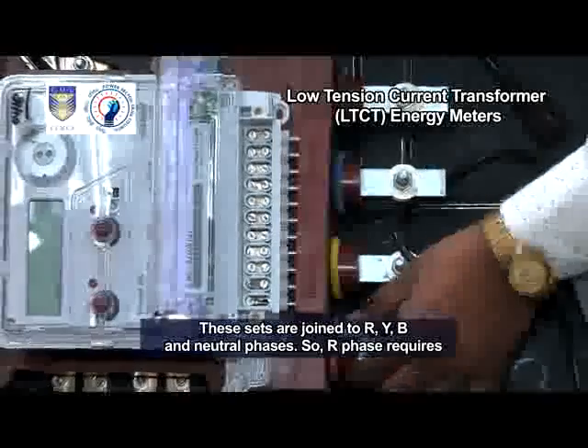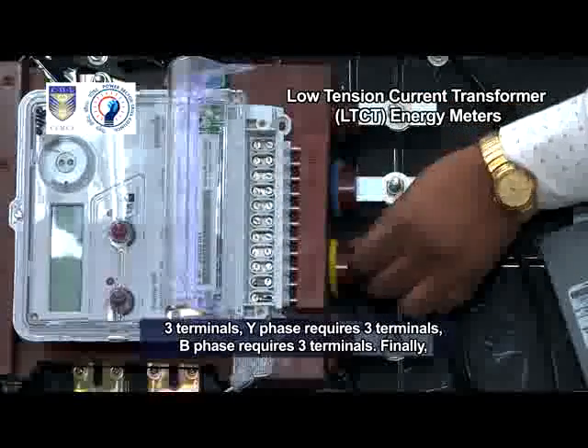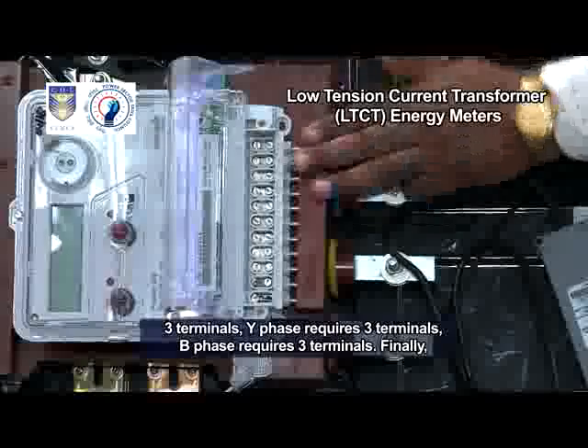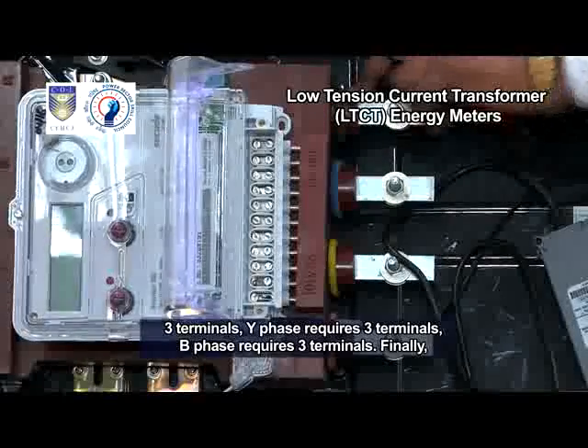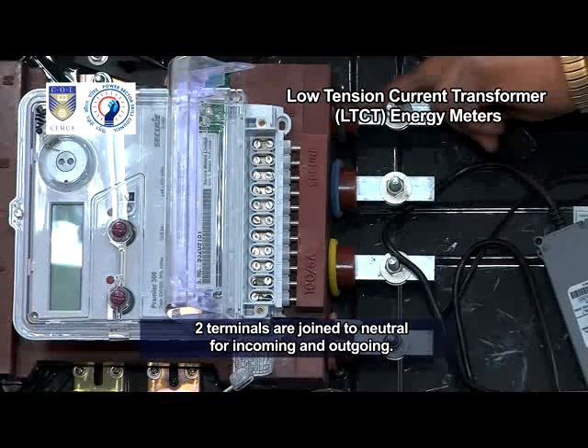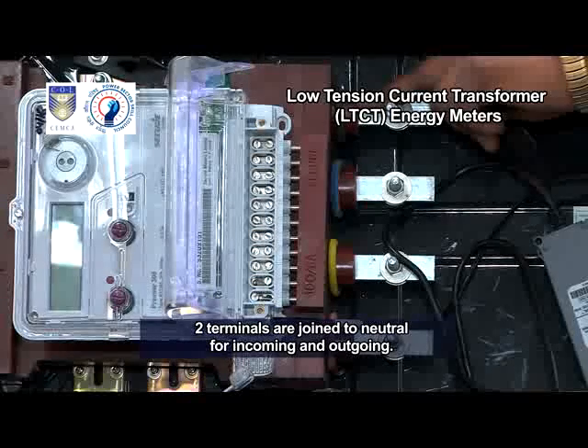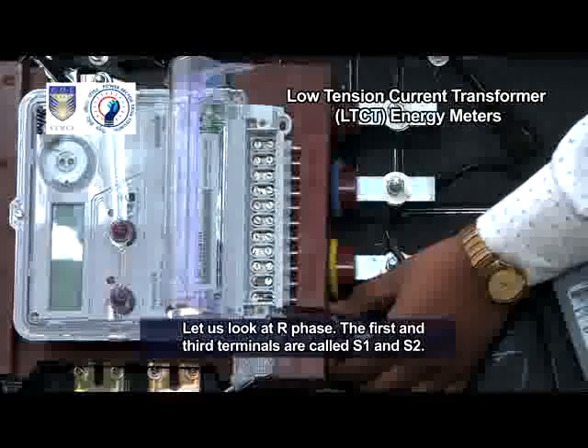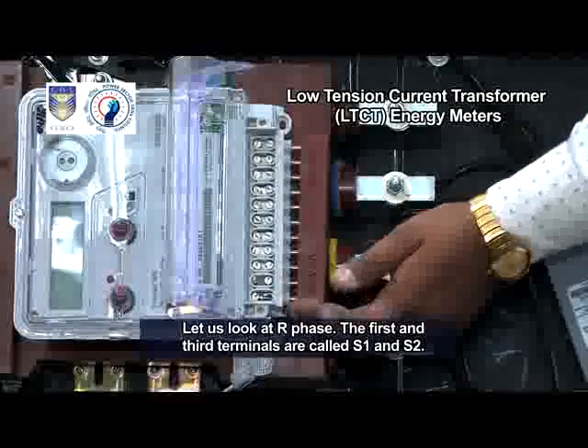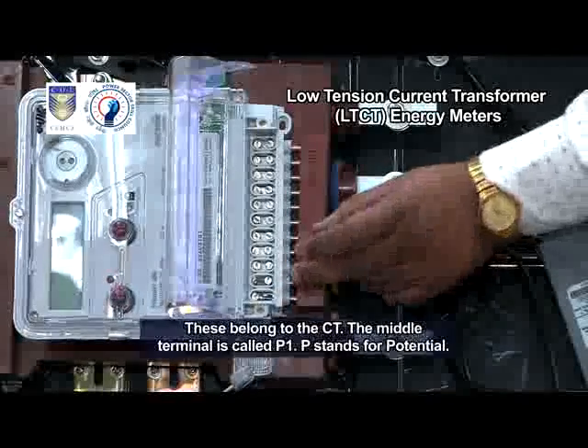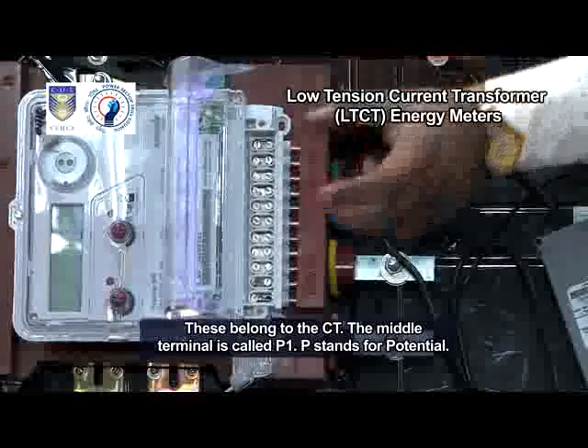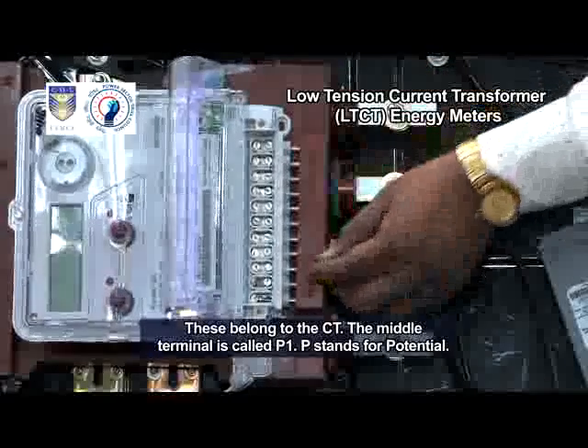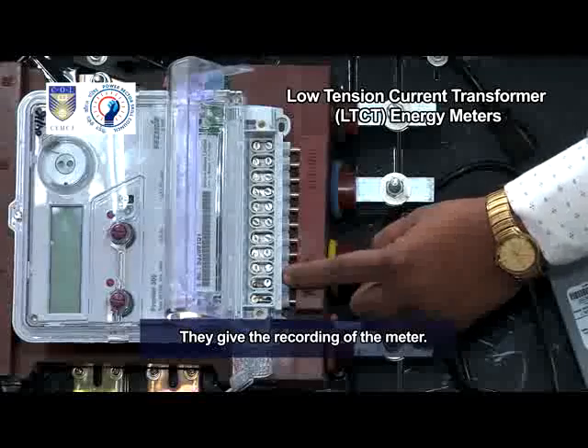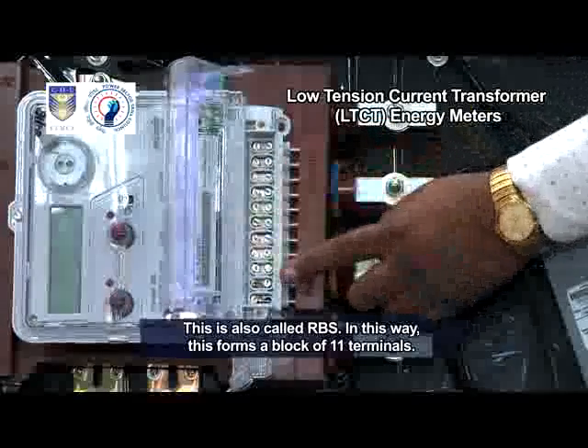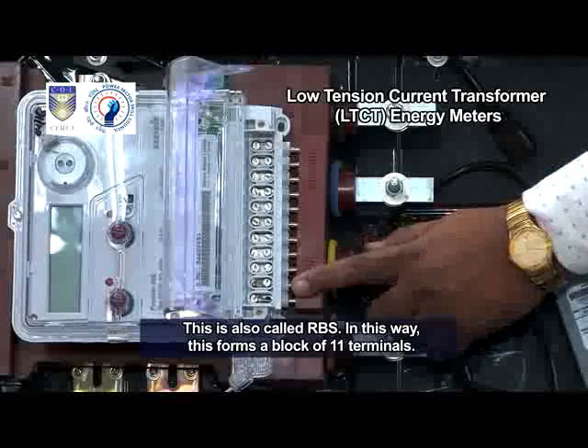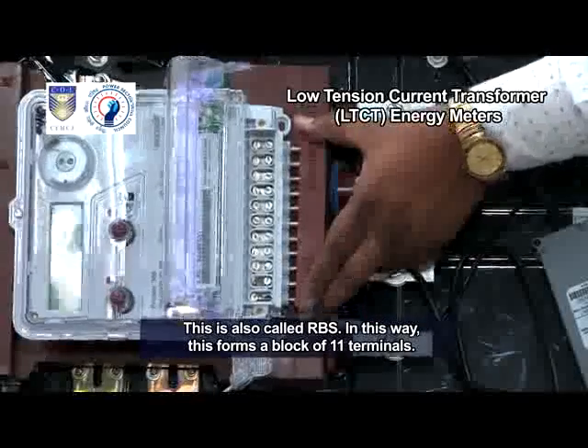So, R phase requires 3 terminals. Y phase requires 3 terminals. B phase requires 3 terminals. Finally, 2 terminals are joined to neutral for incoming and outgoing. Let us look at R phase. The first and third terminals are called S1 and S2. These belong to the CT. The middle terminal is called P1. P stands for potential. They give the recording of the meter. This is also called RBS. In this way, this forms a block of 11 terminals.